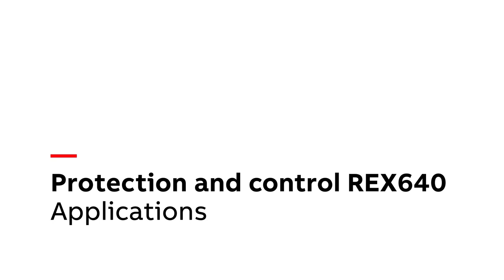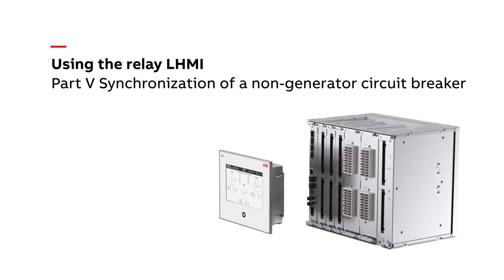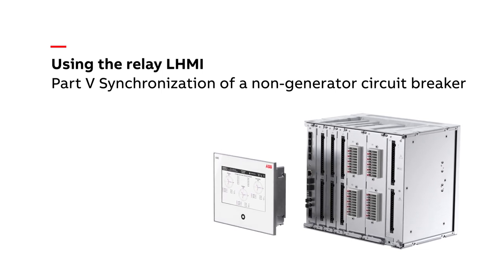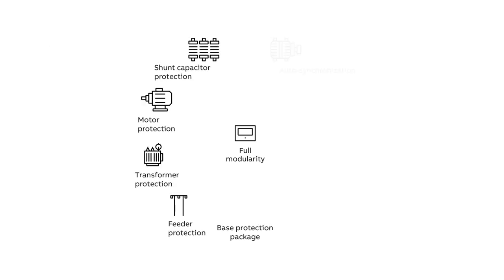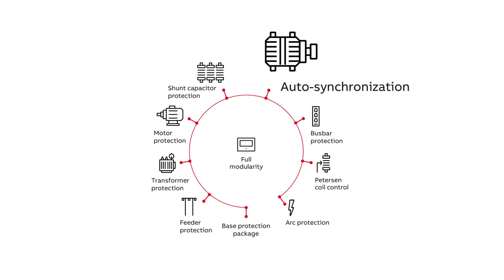Welcome to our short overview of how to synchronize a non-generator circuit breaker, such as a bus sectionalizer or grid incomer, with our user-friendly REX640 protection and control relay. REX640 can handle two different synchronizing scenarios. In this video, we will focus on synchronizing a non-generator circuit breaker. The precondition for using REX640 for non-generator circuit breaker synchronization is that the generator synchronization is also managed by the REX640 relay.